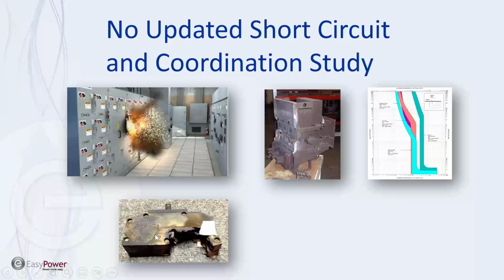This is an overduty breaker that's a 10,000 amp breaker, like the single phase breaker that's in your house. And this is a 35,000 amp fault. So this was in a facility that they did put a sub panel in. They used the sub panel from Home Depot. It looks fine, trips and opens up. You could turn it on and everything came on fine. But when it came time to handle a fault, the fault current was too high and it blew it up. So now you've got more outage time, and hopefully nobody was around to get hurt on that one. So these are called over-duty breakers. They're not going to handle the available fault current.